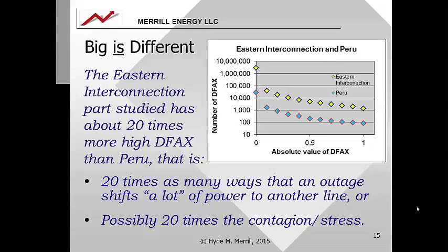Or there are possibly 20 times the contagion and stress that the Peruvian system has. So this leads us to our first conclusion: balkanizing, or subdividing a large system, could increase its robustness by decreasing its vulnerability to cascading failures. Smaller systems may be less vulnerable to internal cascading since there are fewer DFAX, and especially if their values are lower, as for Peru compared to the Eastern Interconnection. This observation is new — I've never seen this said anywhere else.